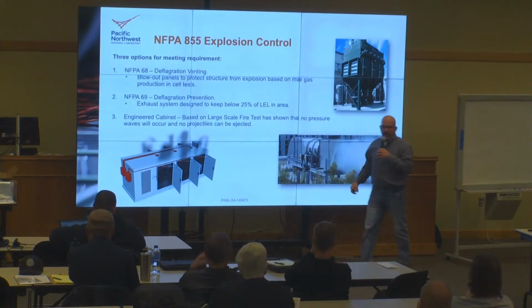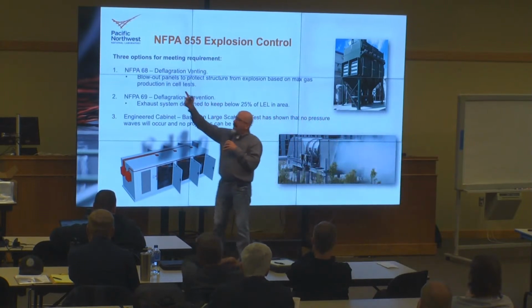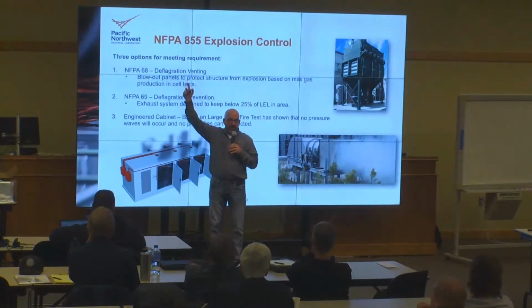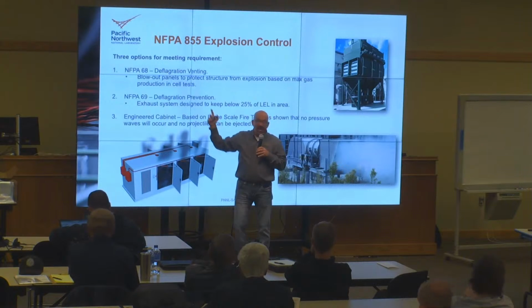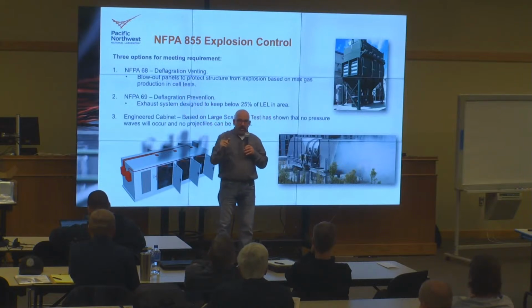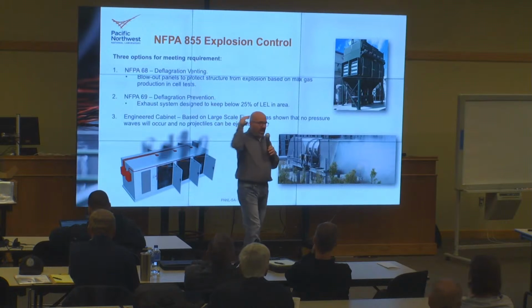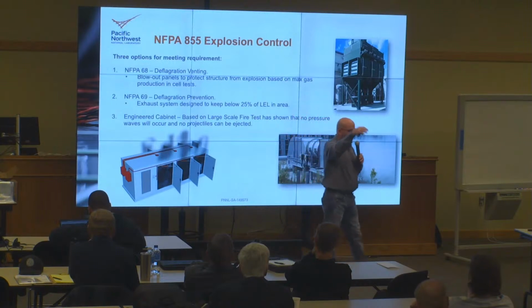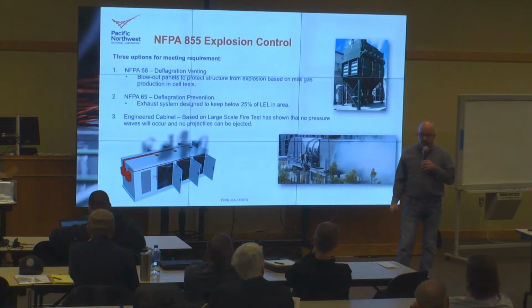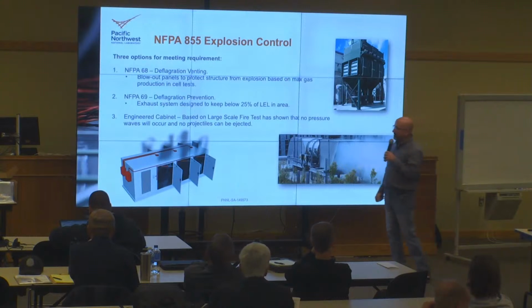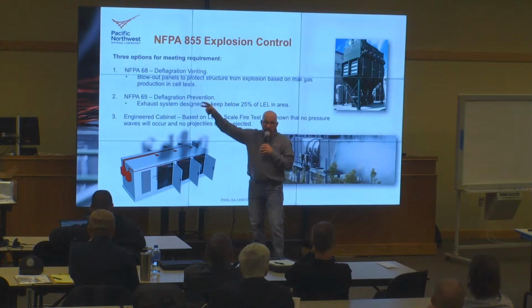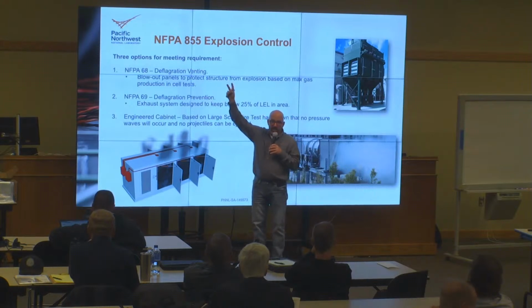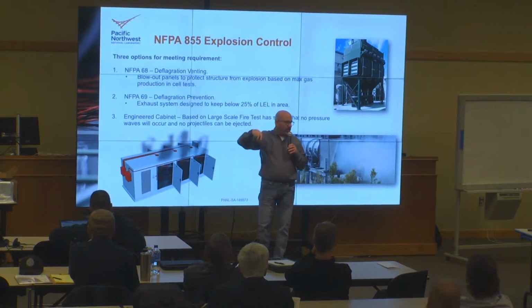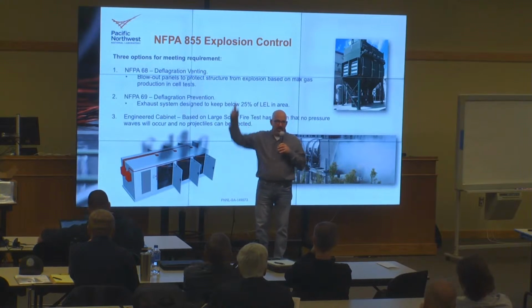Now let me share my personal opinions about these. I don't think this should be allowed by itself — each one of these you could currently do alone. I don't think this is a good idea because it only works when there is an explosion. You could be at 100% of the UFL and no explosion occurs, and who's going to go open that door? Where's the probie? So it's not that I have a problem with people wanting to do an exhaust system — that's fine, active and passive. The truth is, when you really calculate how much square footage you need to release the pressure for hydrogen, there's not enough room on most of these enclosures to do the panels.